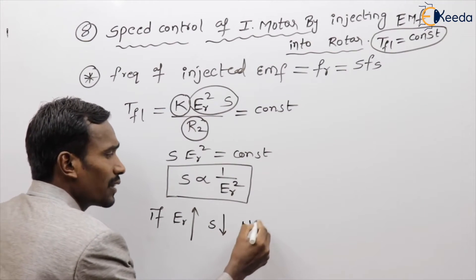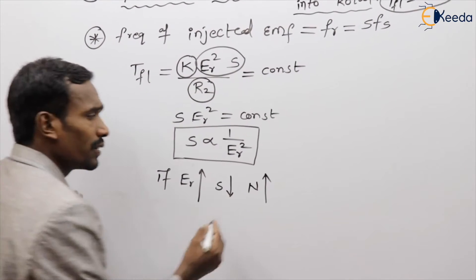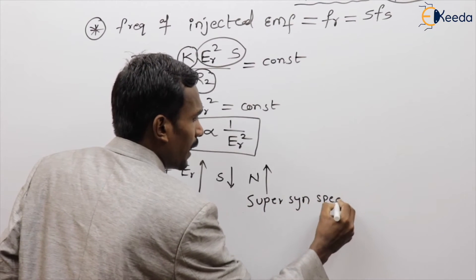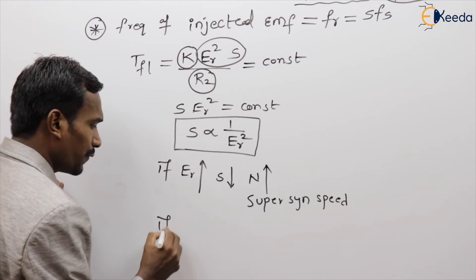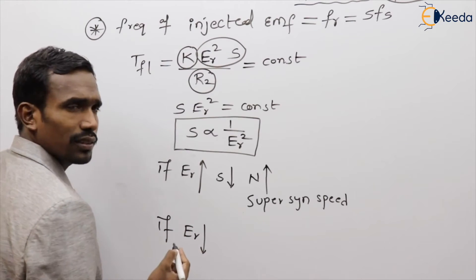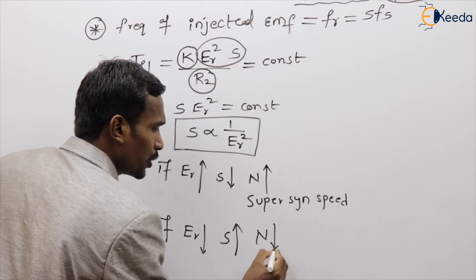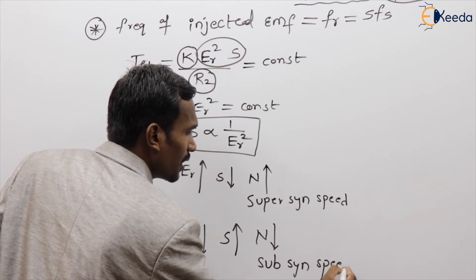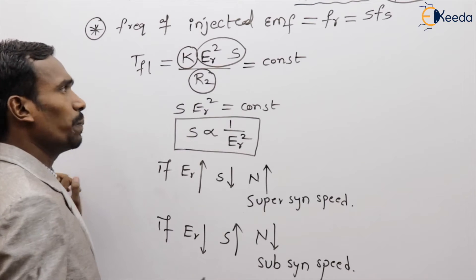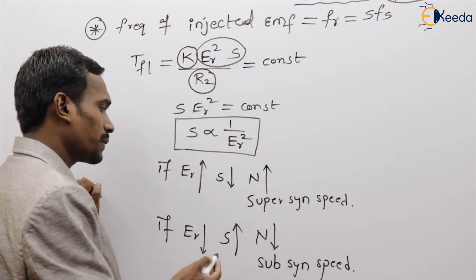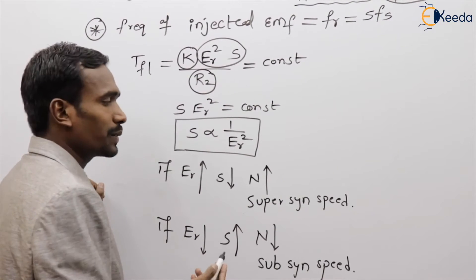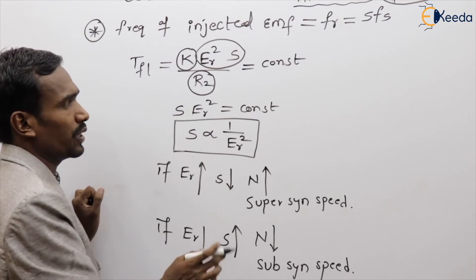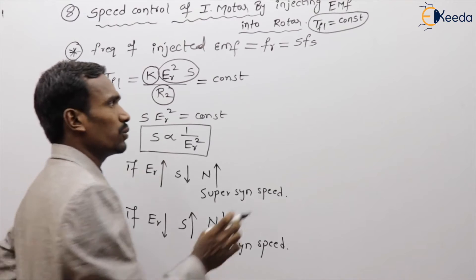If ER increases, slip decreases and speed increases — this is called super-synchronous speed. If ER decreases, speed decreases — this is called sub-synchronous speed. These are the two fundamental outcomes based on whether ER increases or decreases.